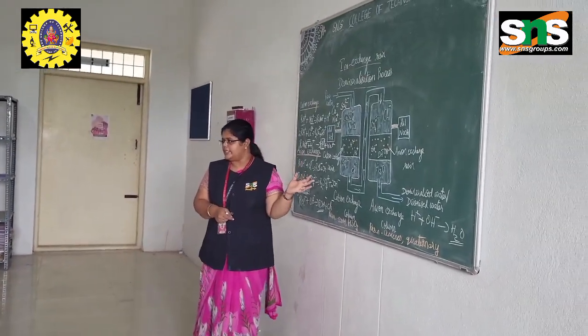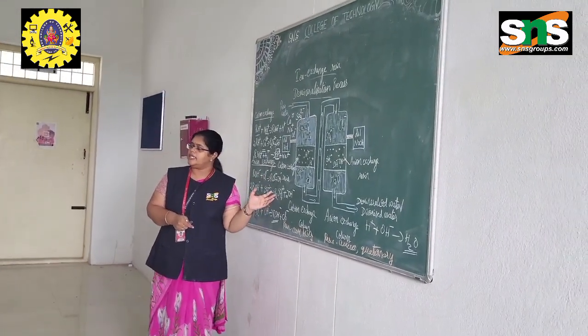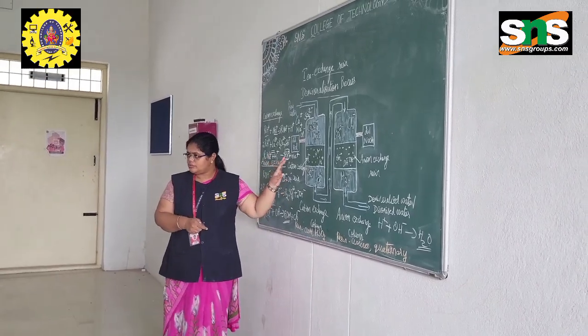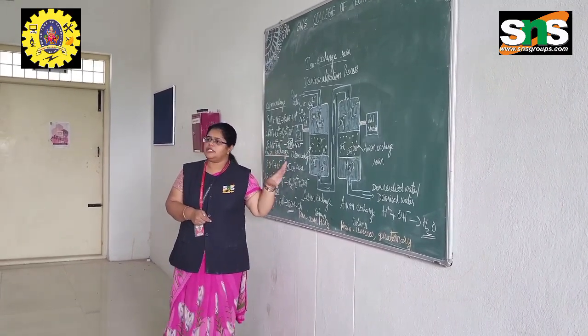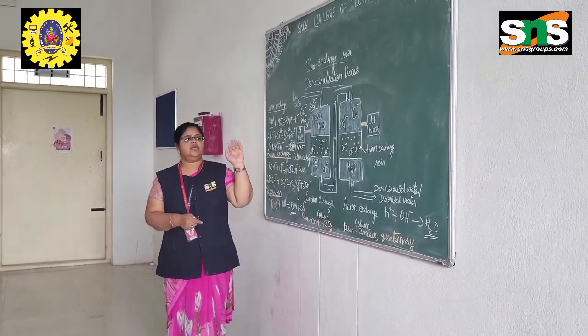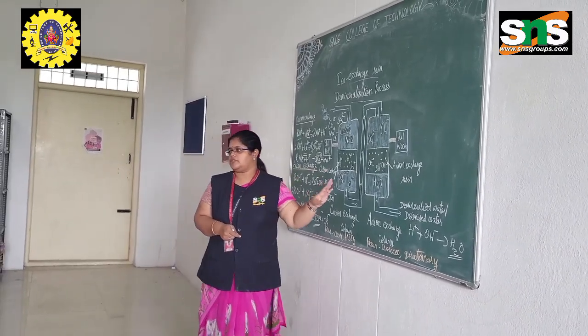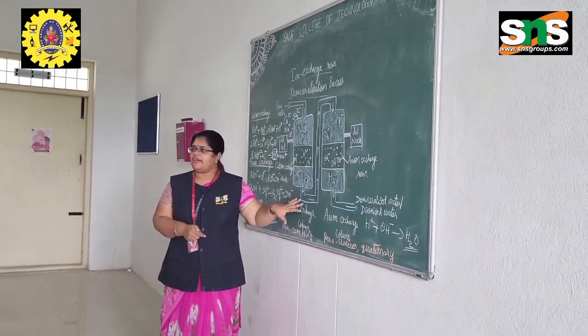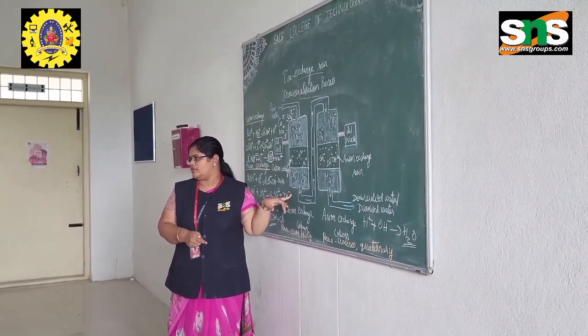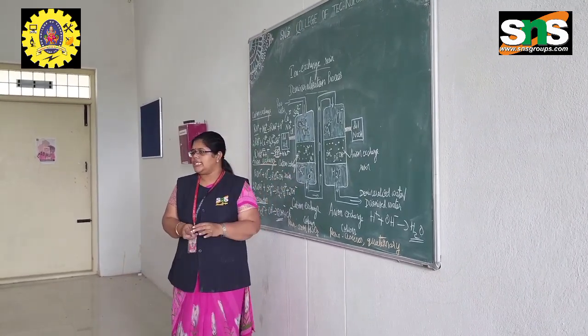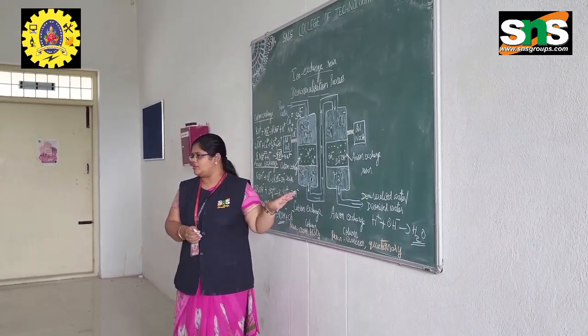Yeah. The main disadvantage is the turbidity. If the water is turbid, it cannot be used in this ion exchange process. First, the turbidity should be removed. Then after that only you can make the water go through this process. Okay. And another thing is, if you have heavy metals present in the water, it is not easy to remove the heavy metals through this process.